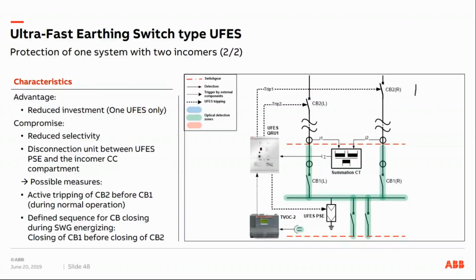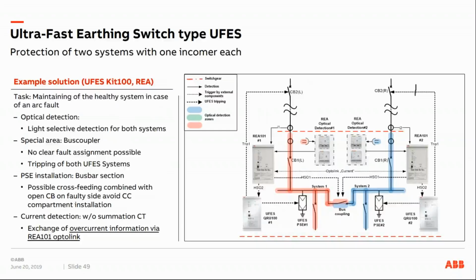So let's move a bit faster. Here we have a more complex system, the protection of two systems with one incomer each. Since each busbar section can also be operated independently, one ultra-fast earthing switch has to be considered for each busbar section. The respective PSEs are connected directly to the left-hand side busbar and the right-hand side busbar, and the UFES is activated by the light sensors of the respective systems.